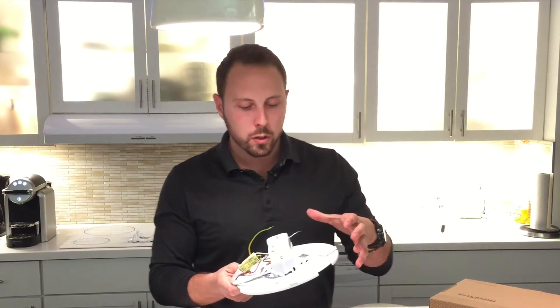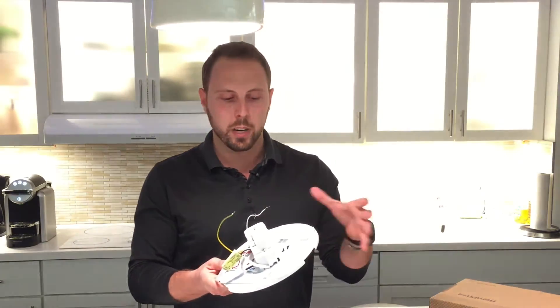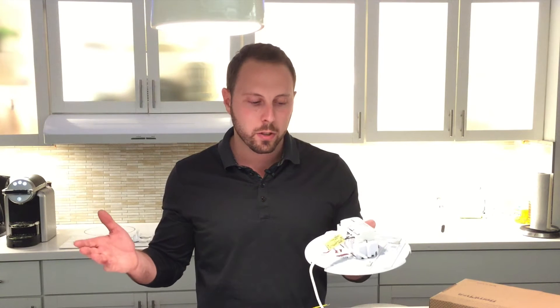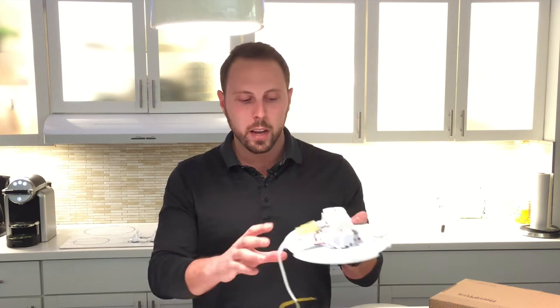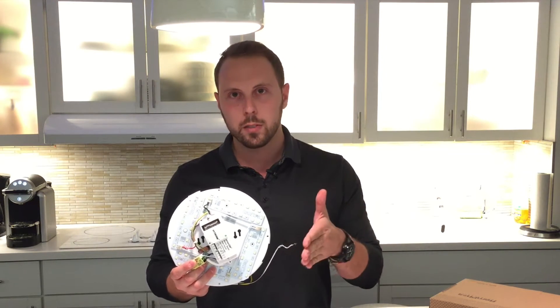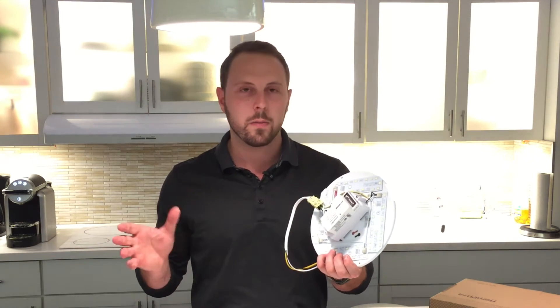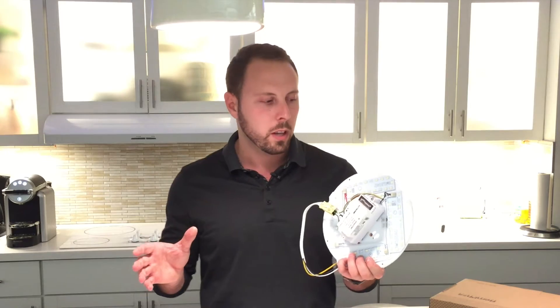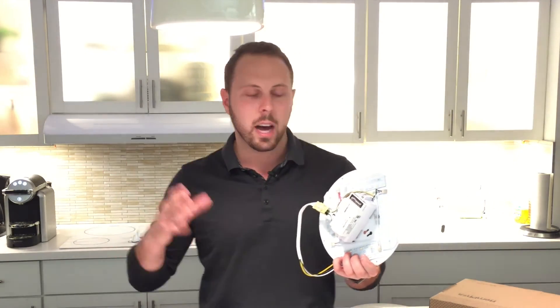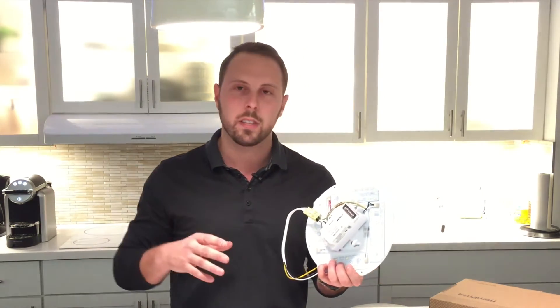When used as a retrofit to replace existing CFL lamps, circline lamps, PL lamps, incandescent lamps — whatever may be in that existing fixture — it can retrofit anything from maybe one 13 watt CFL all the way up to double circlines. It's available in four different lumen packages from 900 lumens up to 3000 lumens, and it's extremely efficient at about 125 to 130 lumens per watt. For example, the 900 lumen disc is about seven watts, and on the high end the 3000 lumen disc is 27 watts.